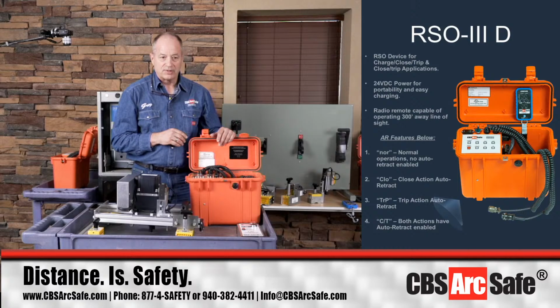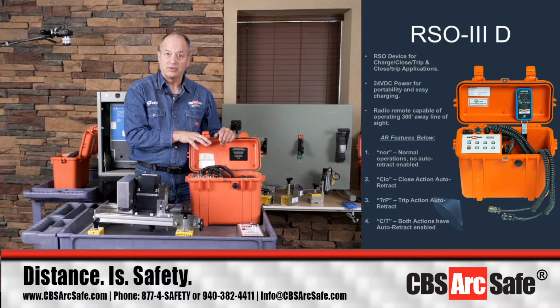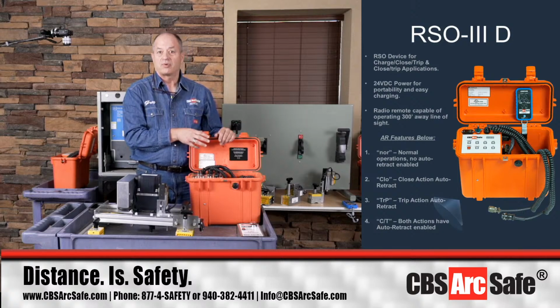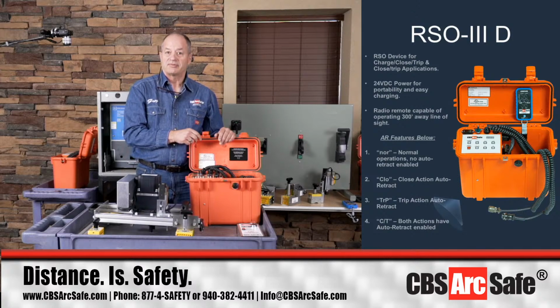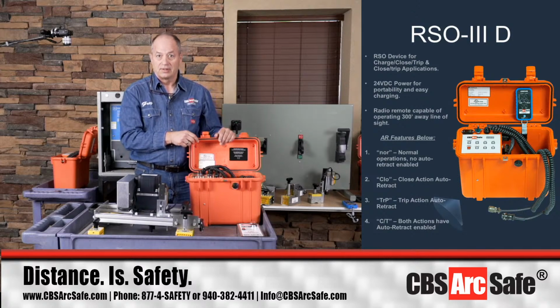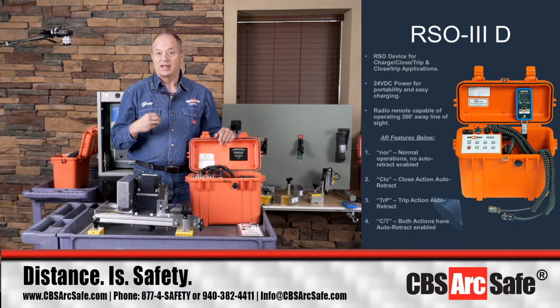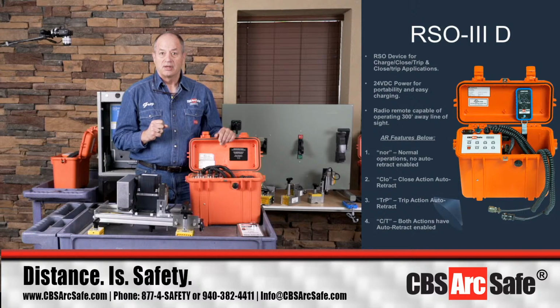The other thing we found out was, as we were going through this, we had to build in automatic return into the RSO-III also, because now when we're dealing with things like a Siemens Allis-Chalmers LA breaker or a Siemens RL breaker, you have to be able to have automatic return on the closing portion. There's other breakers where you have to have automatic return on the trip portion. So these are things that we ran into and had to build functionality into the systems as you, the customers, brought needs to us so that we could meet those needs in your remote racking and remote switching problems.